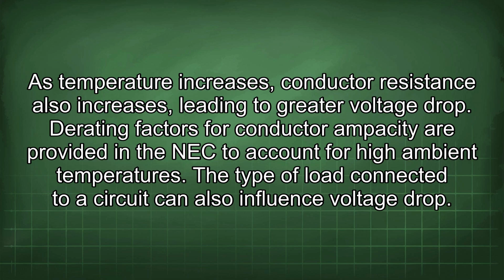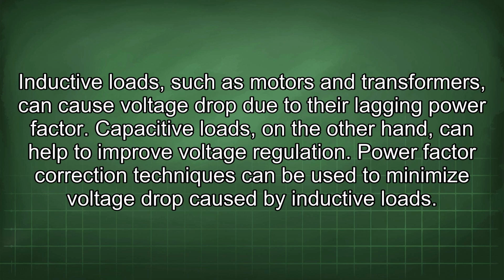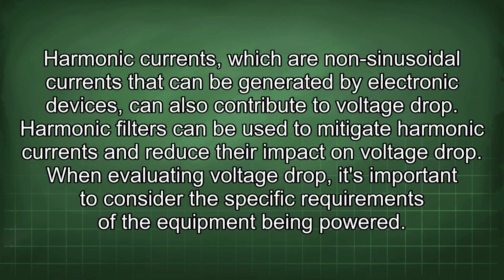The type of load connected to a circuit can also influence voltage drop. Inductive loads, such as motors and transformers, can cause voltage drop due to their lagging power factor. Capacitive loads, on the other hand, can help to improve voltage regulation. Power factor correction techniques can be used to minimize voltage drop caused by inductive loads. Harmonic currents, which are non-sinusoidal currents that can be generated by electronic devices, can also contribute to voltage drop. Harmonic filters can be used to mitigate harmonic currents and reduce their impact on voltage drop.